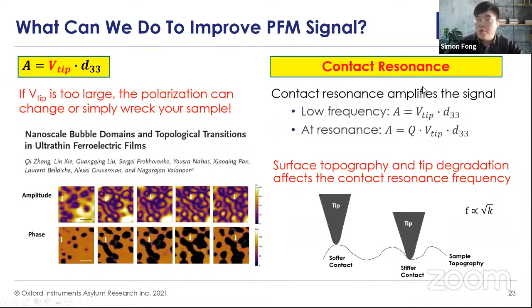The second way to do it is through a phenomenon called contact resonance. It happens when the AC voltage frequency is the same as the resonance frequency of the system, which means when the tip is in touch with the sample. However, this method is only reliable when you have a sample which is really flat, and the contact resonance frequency will be affected if the topography is not flat or if the tip degrades. So based on these two choices, to protect your sample and get better signals, I think contact resonance would be a better choice in comparison with raising the tip voltage.